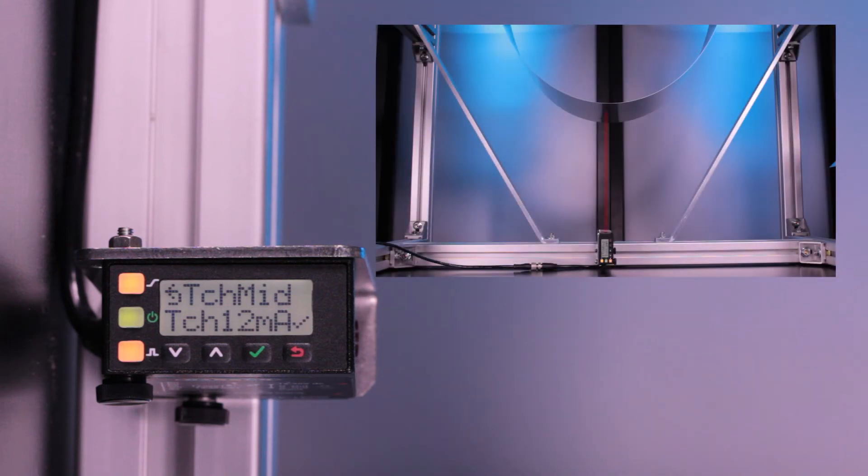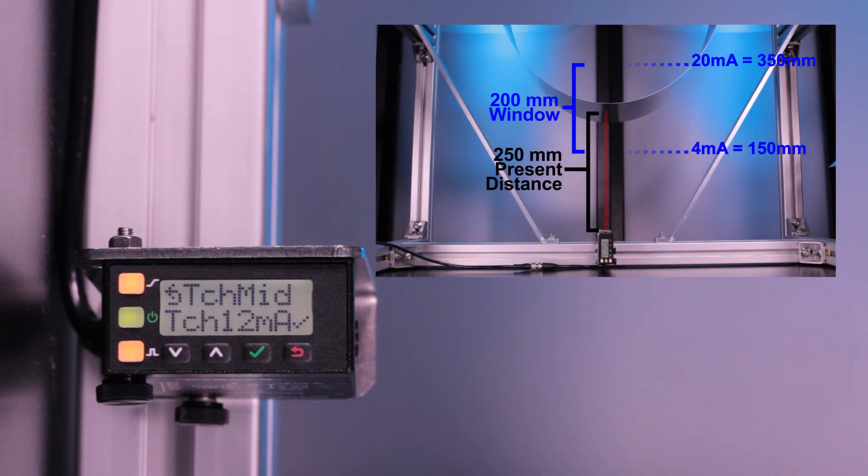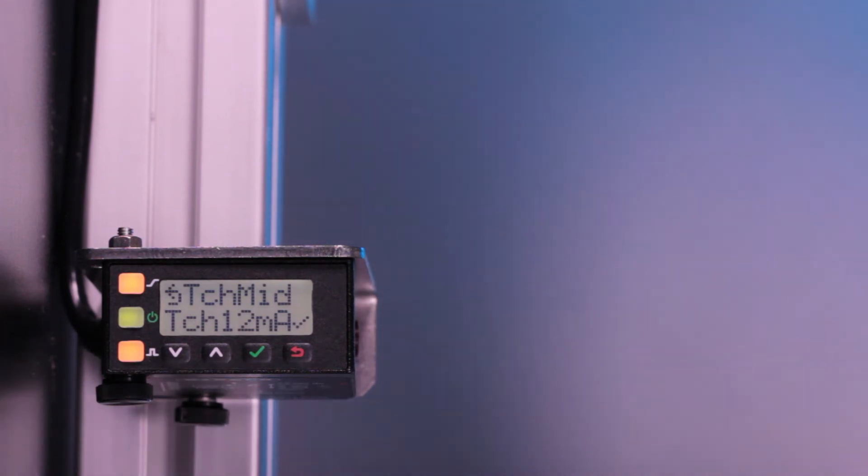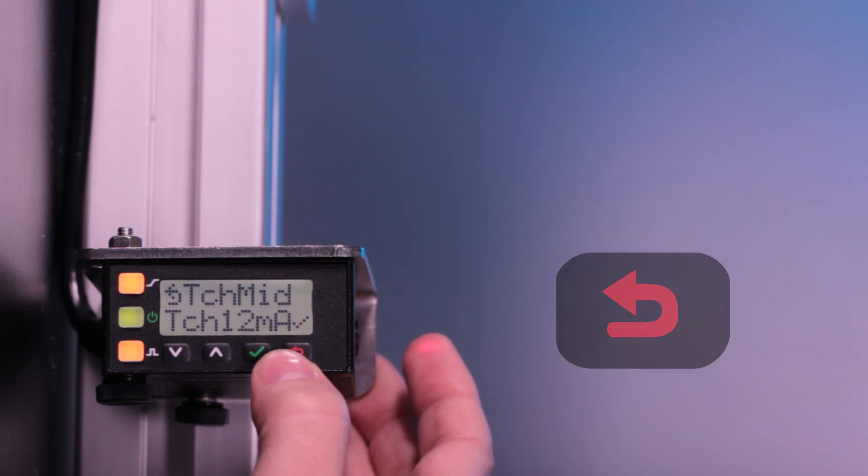In this case, a 200mm window was taught about 250mm. So the 4-20mA analog output is from 150mm to 350mm. Holding back will return us to the run screen.